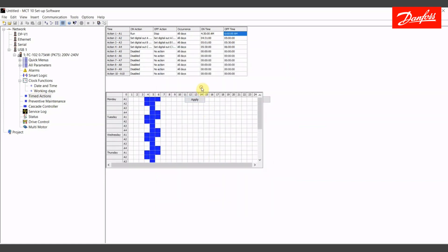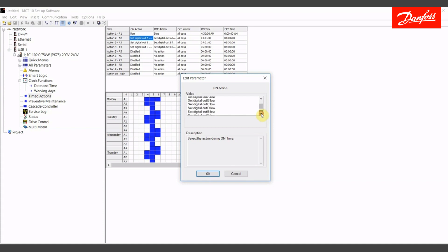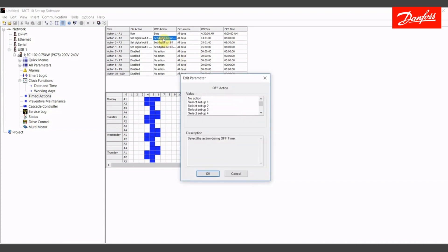We move on to our second event. This is where I want to control zone A or turn it on. To control outputs on the drive, we use these selections here. Set digital output A high. Setting an output high is the same thing as saying to turn it on or activate the output. We'll later define what is actually output A, B, C, and so on. The off action will be to set that output low or turn it off. That'll be zone one.